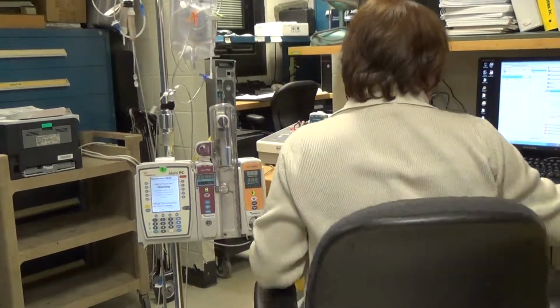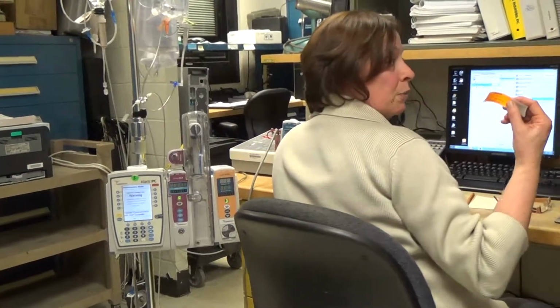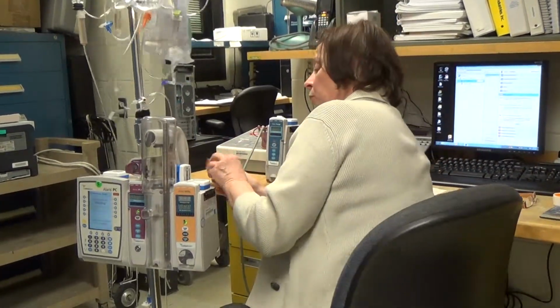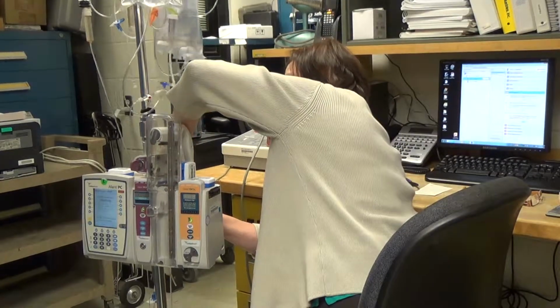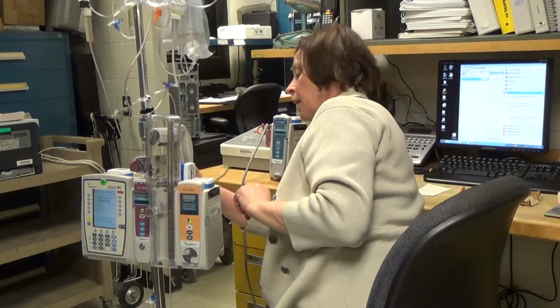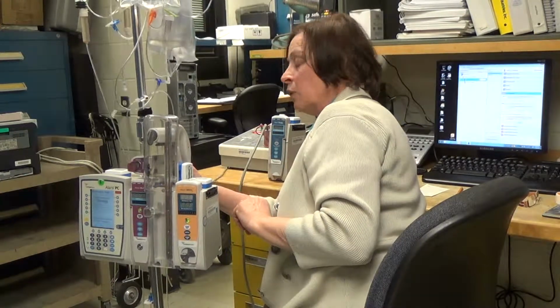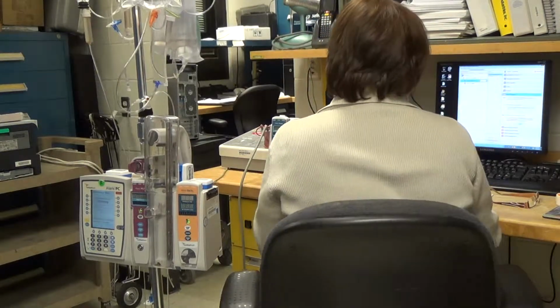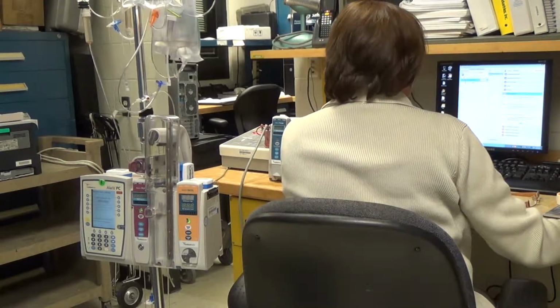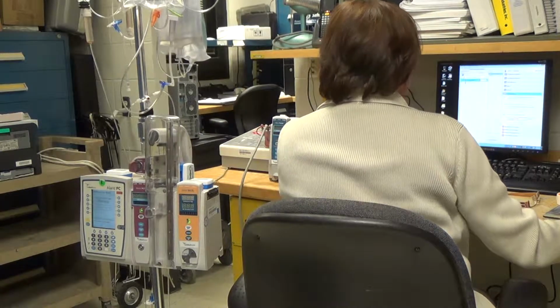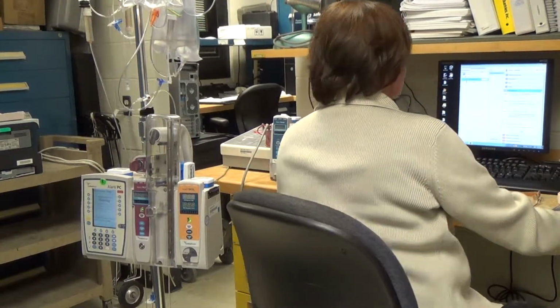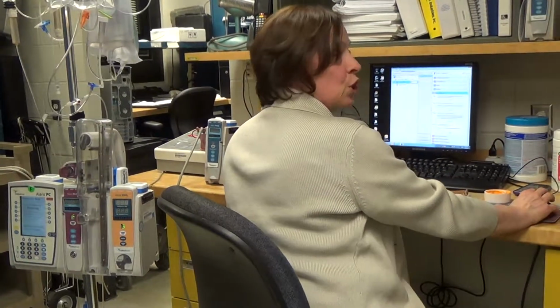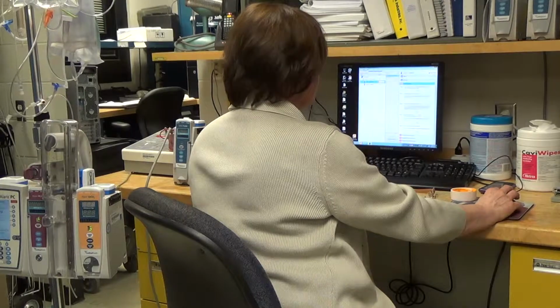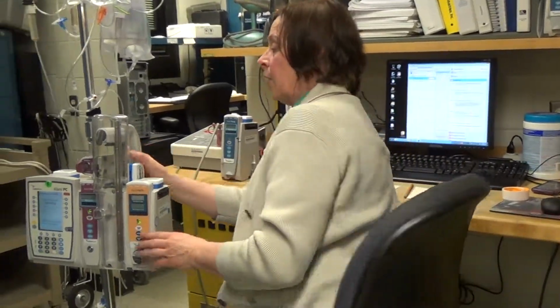close things up, and at that point you get your PM sticker, which is attached to the back of the pump. This way it is clear to the staff that everything is up to date, and if Joint Commission comes, they will be able to readily see that it's been PM'd and it's all due and in correct timing. The next thing is you can set on your computer your new PM date so that it will show up next year on the PM list. At this point, you are finished with your PM and the device can go back into service.